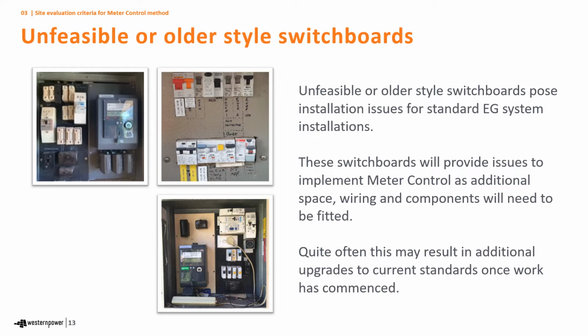And what is unfeasible or old style switchboards? Why are these not suitable? These sites pose an installation issue even for your standard embedded generation system, standard inverter installations. So they will also provide more issues if you want to include meter control, as additional space and wiring components will need to be fitted. Quite often, this may result in additional upgrades to the current standards once work has commenced.